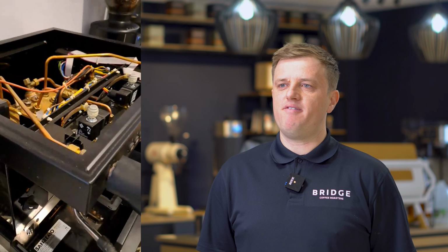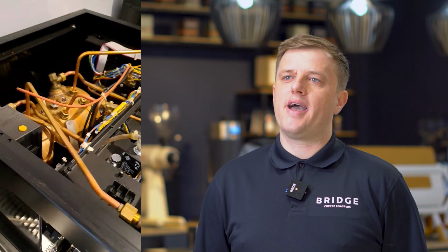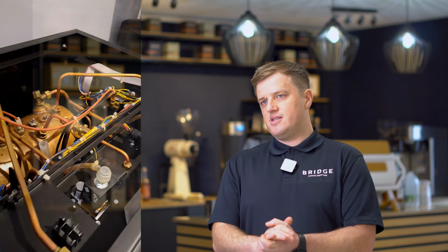All of our engineers are certified through an external company to carry out a PSSR inspection, so we are following the governing body on what they require. First of all, we strip the machine down, looking for any defects on the boiler, so any dents externally. We also use a camera to go inside the boiler. We're looking for scale build-up, defects around the heat exchange, and also any defects inside the boiler.